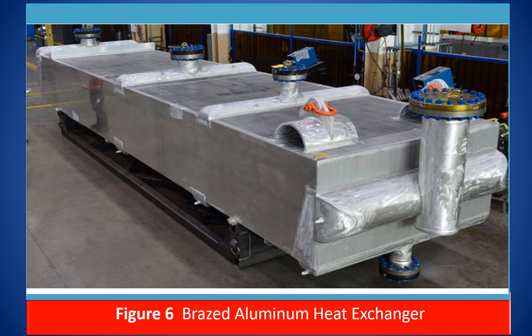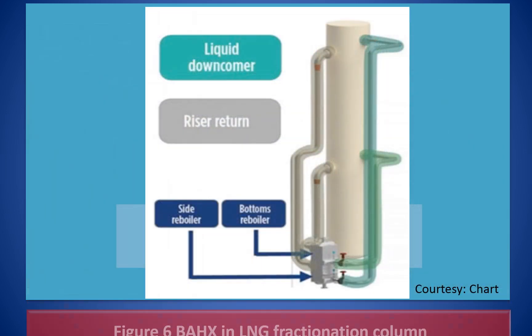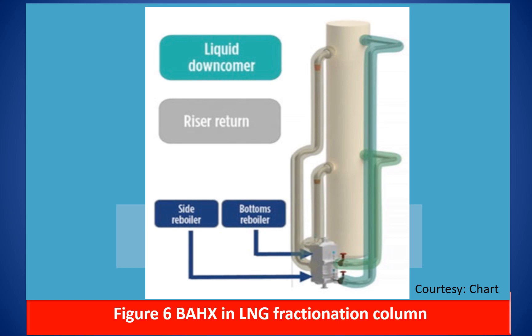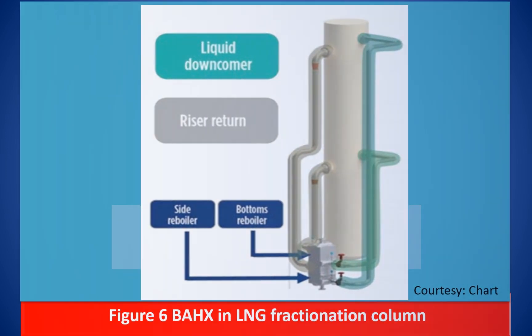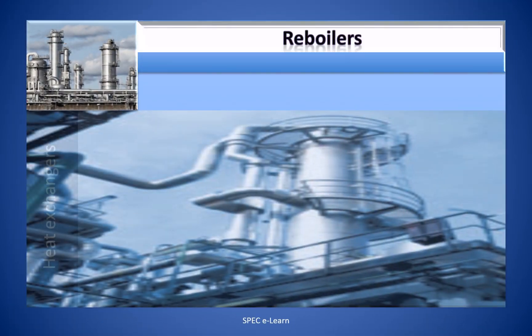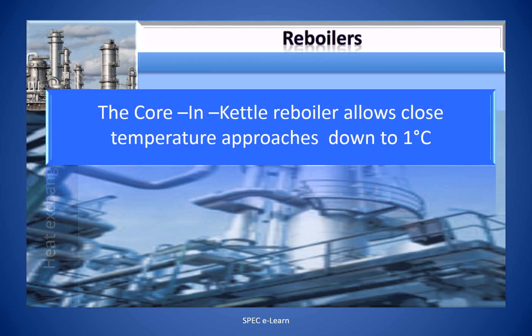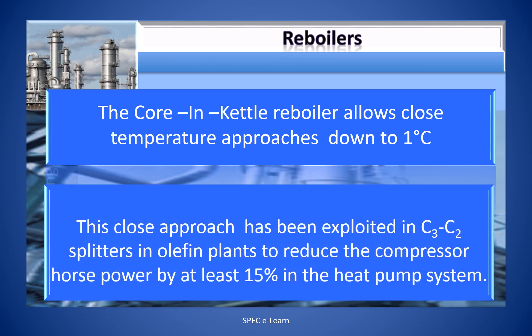This figure shows a fully assembled core in kettle brazed aluminum heat exchanger ready after fabrication for dispatch. Another example shows a core in kettle brazed aluminum heat exchanger installed in a natural gas liquid fractionation column, demonstrating how core in kettle technology has progressed and found new applications in cryogenic industries. The core in kettle reboiler allows close temperature approaches down to 1°C. This close approach has been exploited in C3 and C2 splitters and similar plants to reduce compressor horsepower by at least 15% in the heat pump system.